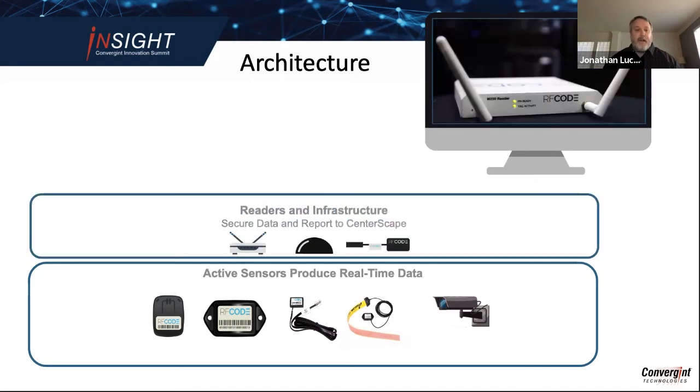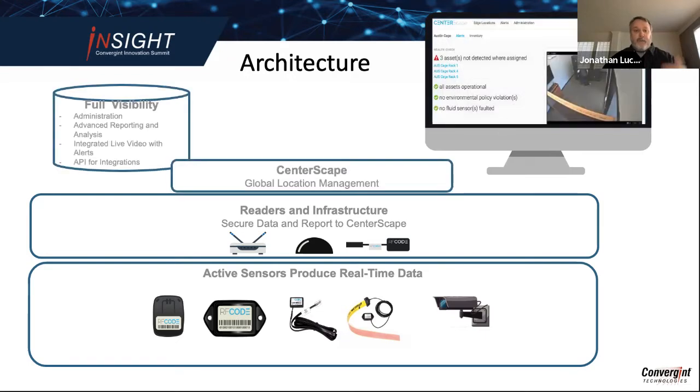And once it goes up into the air, it goes to a reader infrastructure. And a reader, you can see on the little monitor that popped up in that icon, shows what a reader looks like. This collects all the data. You deploy about one of these every 3,500 square feet of white space for a data center, and then probably one every 10 or 12,000 square feet for open air. Any place where you think equipment might move around to, that's where we place a little reader, and it's networked. One's over PoE, really simple to use.